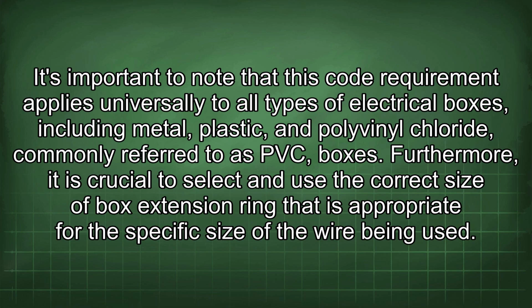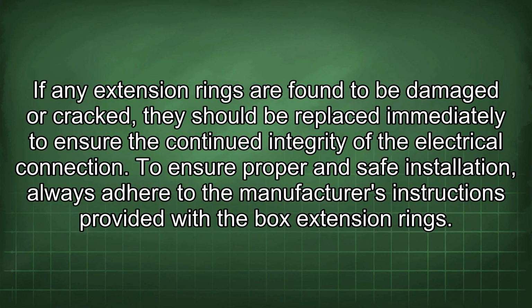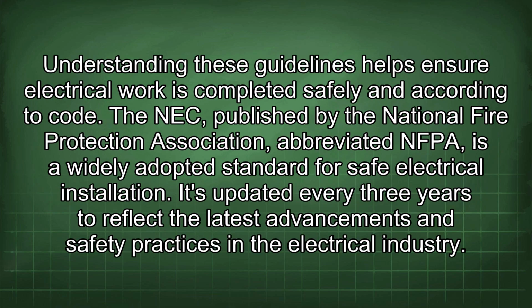Furthermore, it is crucial to select and use the correct size of box extension ring that is appropriate for the specific size of the wire being used. If any extension rings are found to be damaged or cracked, they should be replaced immediately to ensure the continued integrity of the electrical connection. To ensure proper and safe installation, always adhere to the manufacturer's instructions provided with the box extension rings. Understanding these guidelines helps ensure electrical work is completed safely and according to code.